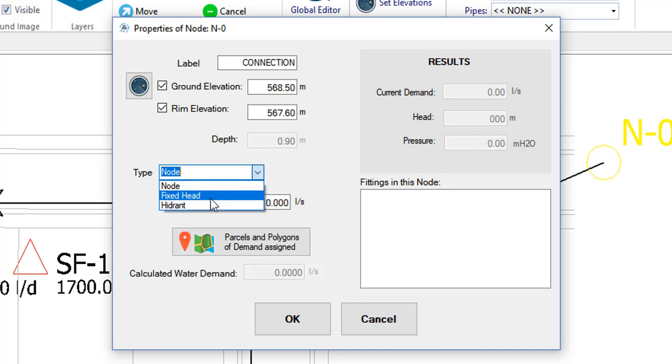The fixed head node is the one that will represent the point or points of water supply in the network. Since the calculations are made for a peak flow, that is to say, for a specific moment of a typical day, it is assumed that from this node a fixed piezometric head is maintained and that it has the capacity to introduce to the system a flow equal to the corresponding actual demand.